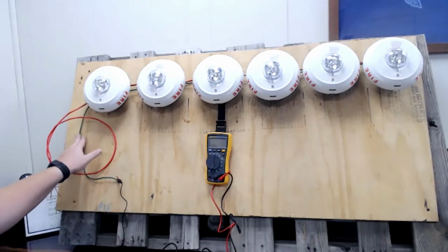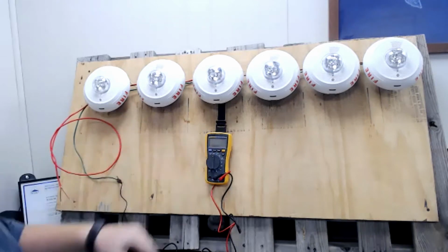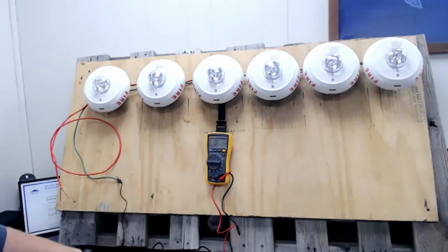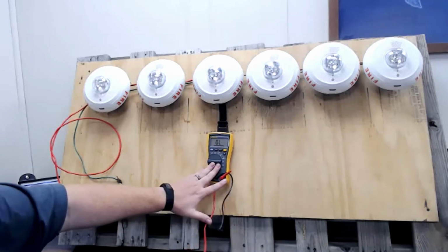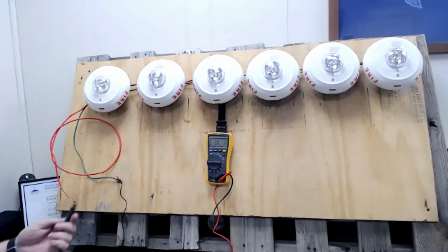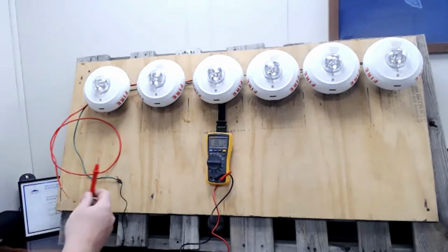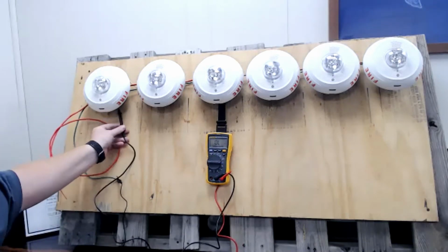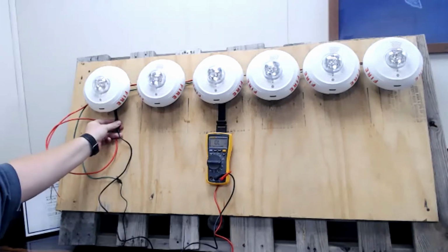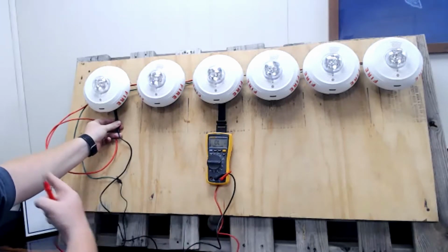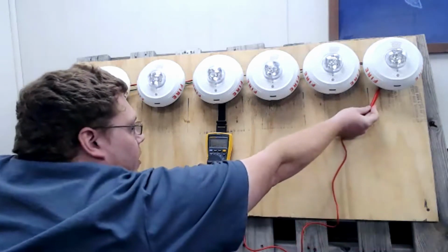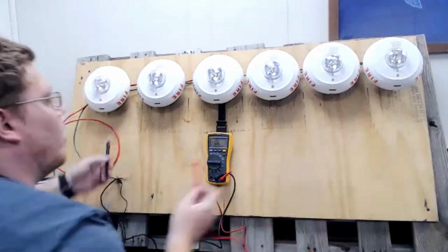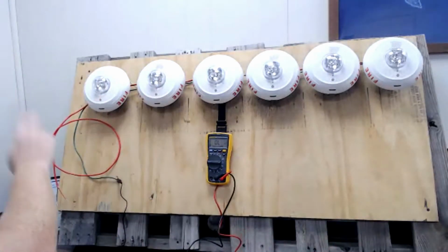So I had to create this ground circuit to connect from box to box so that I could do things like have a ground fault. I'll show you real quick. If I have my meter set on the ohm setting, this is that Greek omega letter, I'm going to take one of my meter leads and I'll touch this first box. I know you can't really see it because the device is in the way, but I just took the end of the meter lead and it's touching the box. I'm going to go all the way to the other end and I'm touching the other box, and my meter reads 0.1 ohms because there's a solid connection via that green wire going from box to box to box.